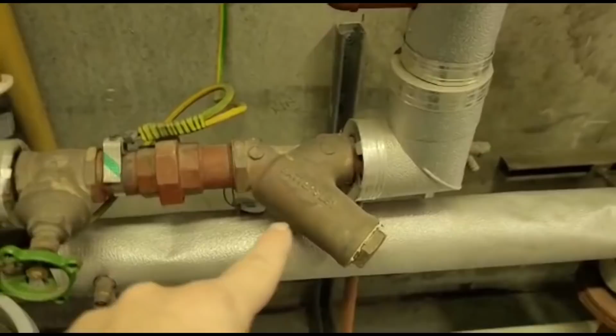And then down to a strainer here where we catch the muck. I did that not so long back. I always do it on servicing and whatnot when I'm servicing the plant room, but also on isolation. It's all pretty old, this isolation in these plant rooms now - coming up to 16, 17 years old, and not all of it is the best, so it's always better to cool the water off, and then if it doesn't isolate, you haven't got a couple of bar of pressure flying out at you.